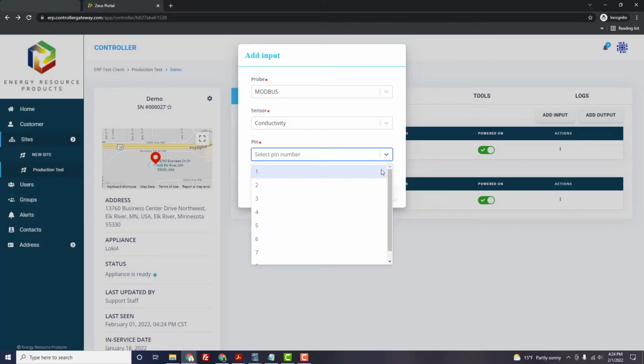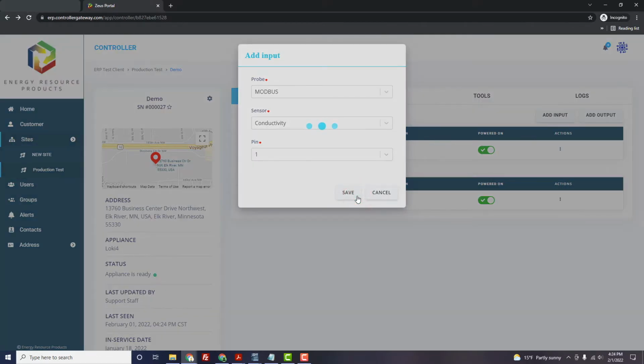Next, select the pin. For Modbus, this will be the slave address programmed in the probe. You may select any one of the available numbers in the drop-down list. After a number is used, it will not be presented when programming additional Modbus probes. Select Save.